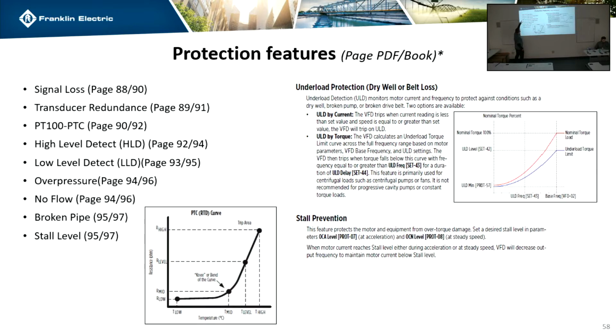High level detect, low level detect, that's your amperage. So low level detect is defaulted on. I'm not sure about high level detect. Both fully adjustable. Basically, it's just saying you're above your set point. Let's see, 94, 95 should be. Quick question on this PT100. Is that just motor temperature? I'm not positive. Yes. Otherwise, it's just a calculation, right? Yeah. So it can't take just a regular temperature input to control? You could, but it would be a transducer setup. You could. Temperature is one of the options in the PID.